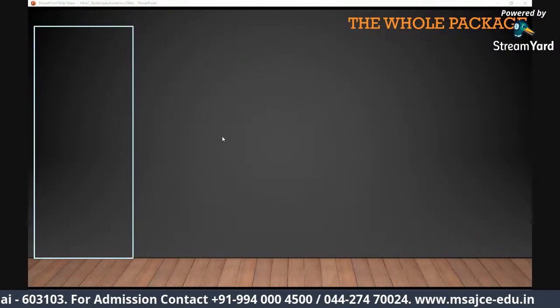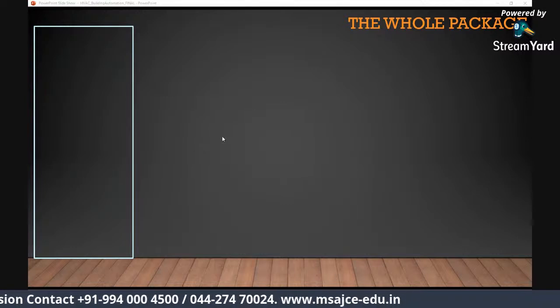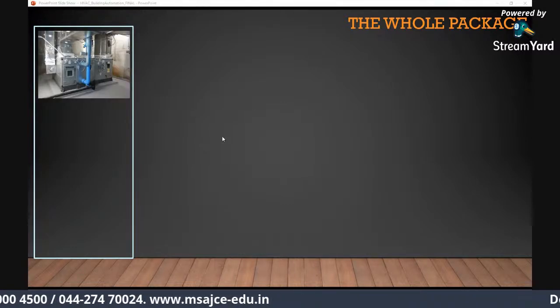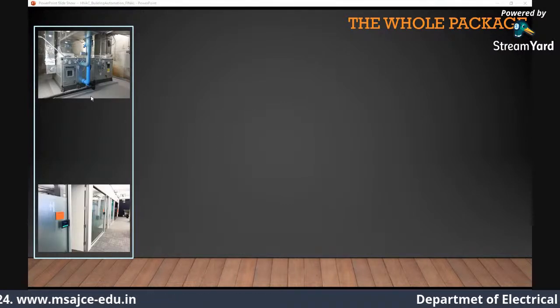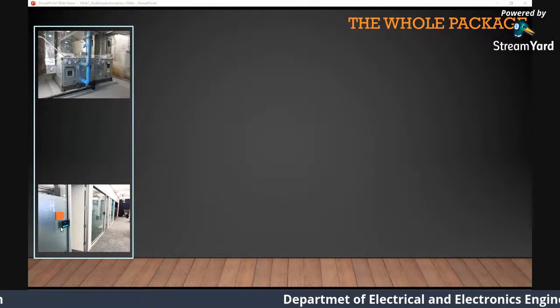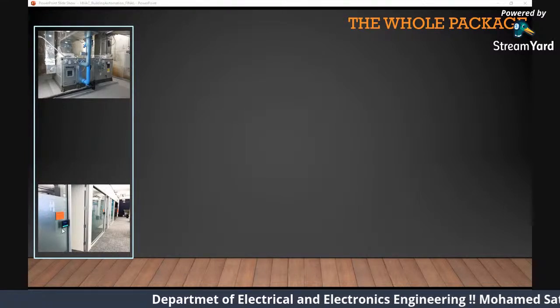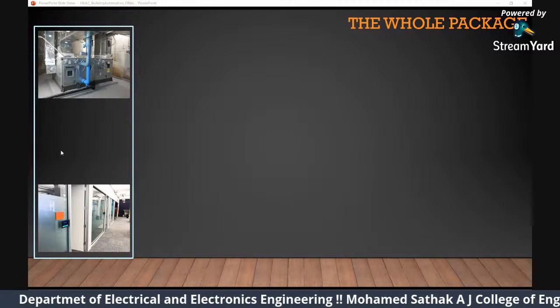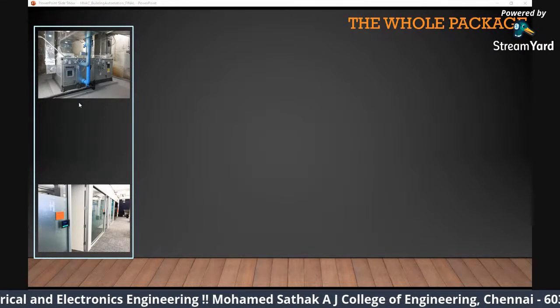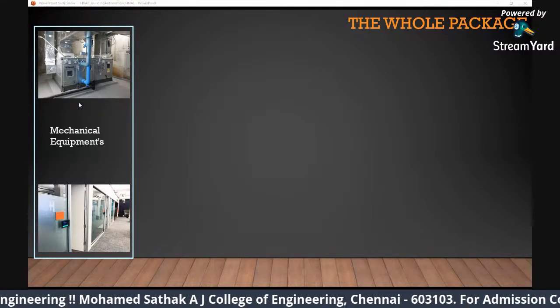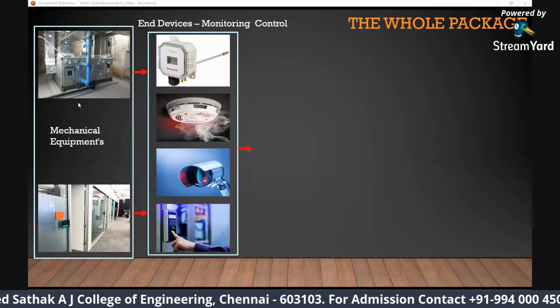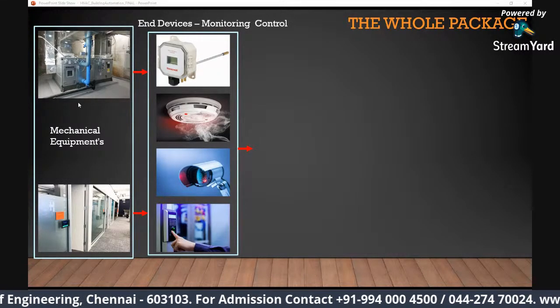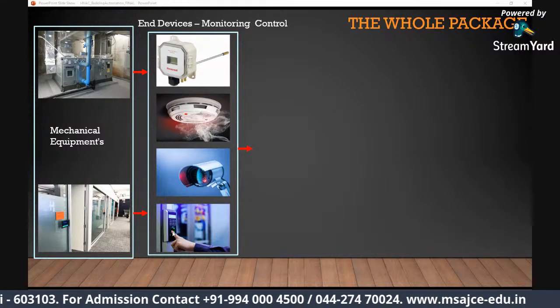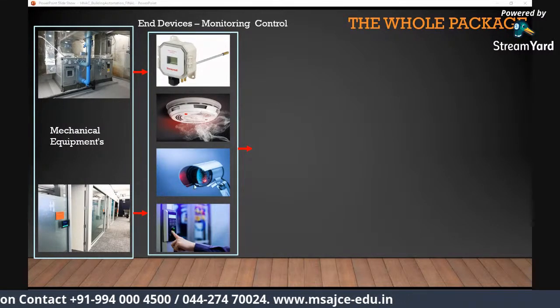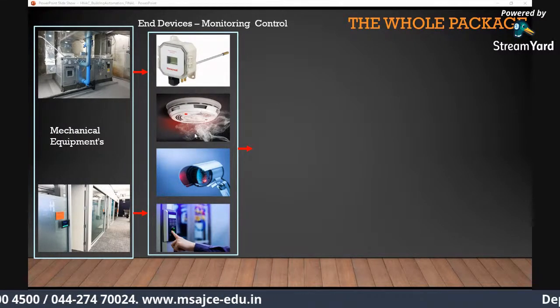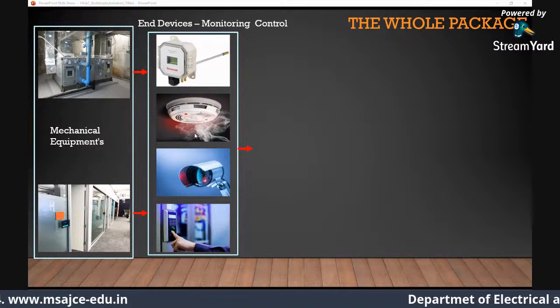Okay, so we saw the whole package of the HVAC system. Now we'll see the whole package for your building automation system. So we have all your mechanical equipment, AHU, chiller, boiler. This is your door. If you can see the access, the door is mechanical equipment. Let's consider there is mechanical equipment and you want to control that. You don't want to turn it on manually. So we use sensors to measure your flow, temperature, and let's say security or access control, your door access, biometrics at the bottom, cameras, smoke detectors. All these are end devices for monitoring, measuring and control.